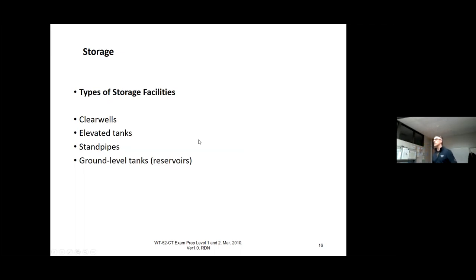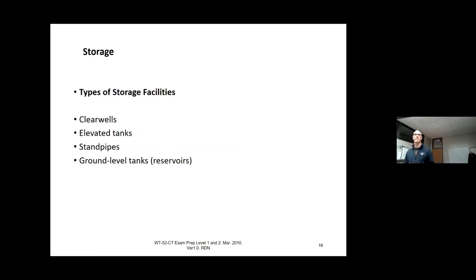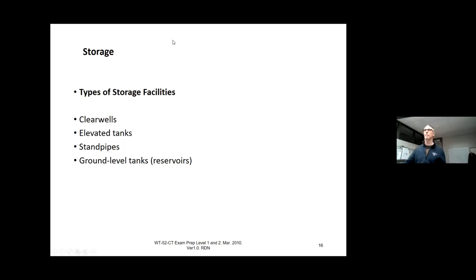There are a number of different types of storage facilities, largely dictated by where you are in the world. Clear wells are usually at the treatment plant — that's your first tank, and a lot of times the clear well water is used for backwash for the filter system. You also have elevated tanks — if you live in a very flat area, you're going to end up with those. If it's flat there's no gravity, so you need to get the water up high to feed down.